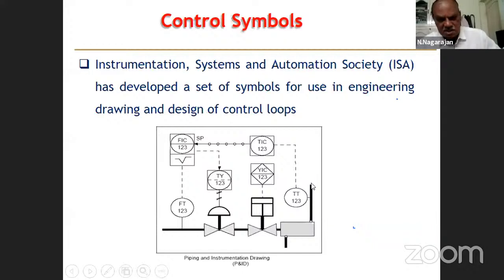According to the outlet temperature requirements, the flow has to be varied. You understand? So temperature is the controlled variable, and this should be maintained at a certain level. The temperature transmitter measures and gives the signal as a set point to the flow controller. The flow is adjusted to match the set point, finally through the control valve. This is the DCS symbol. The dotted line, I will tell you what all these are. This is a shutdown valve, meaning the diamond inside a square is a trip signal. Trip action is taken. If this symbol is shown, that means this device is used for shutdown.